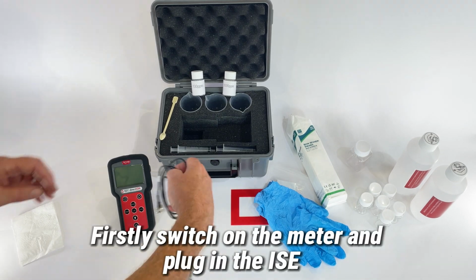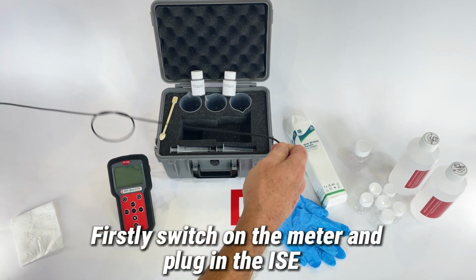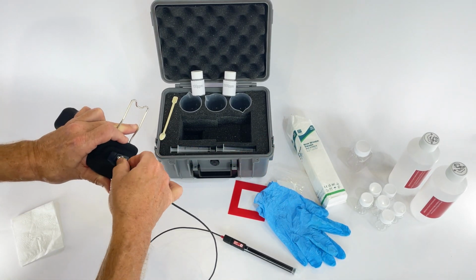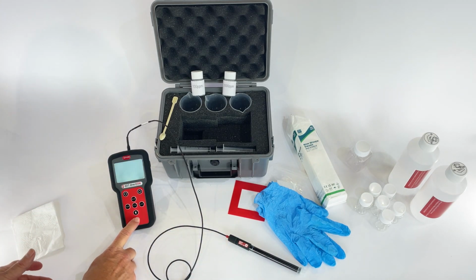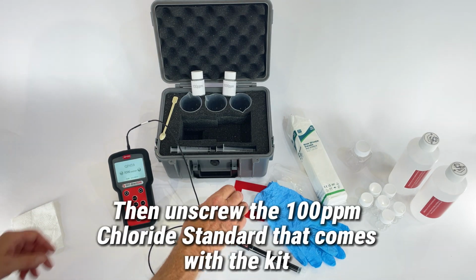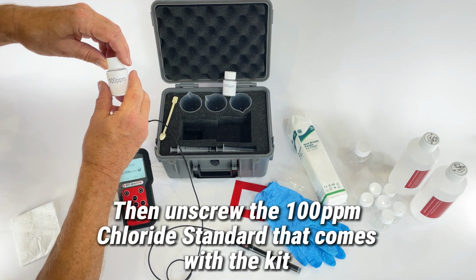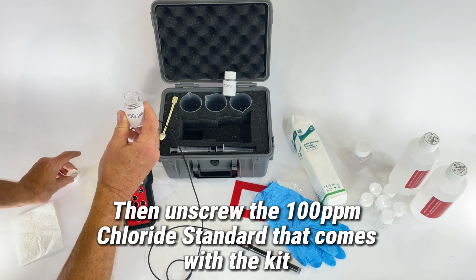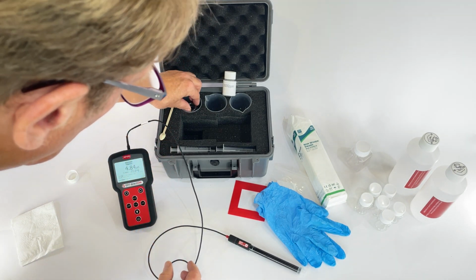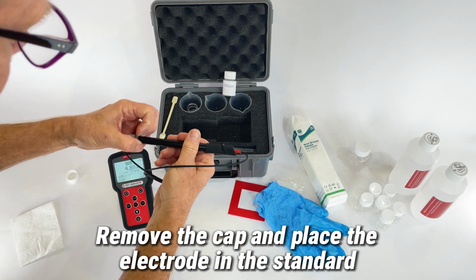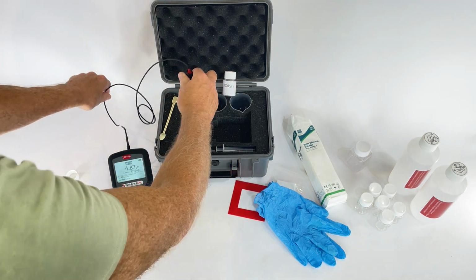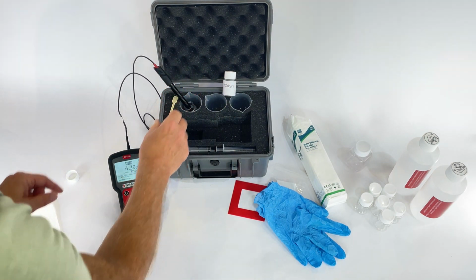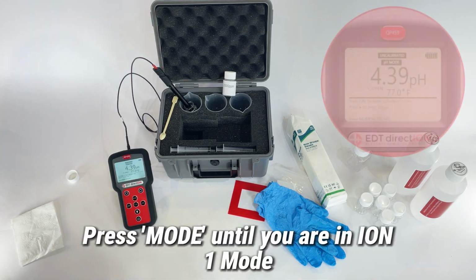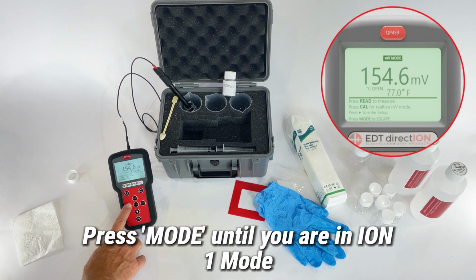Firstly, switch on the meter and plug in the ISE. Then unscrew the 100 ppm chloride standard that comes with the kit. Remove the cap and place the electrode in the standard. Press mode until you are in ion 1 mode.